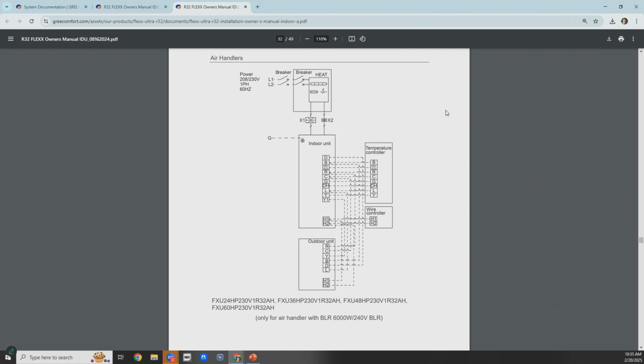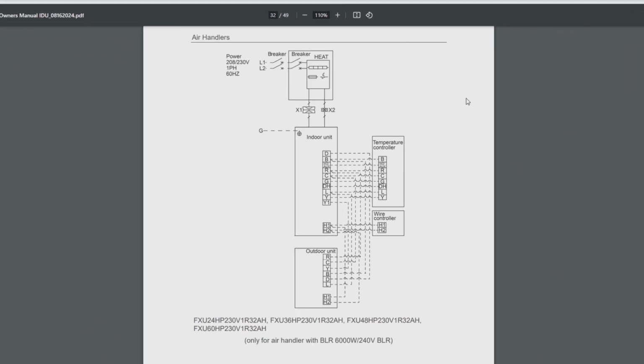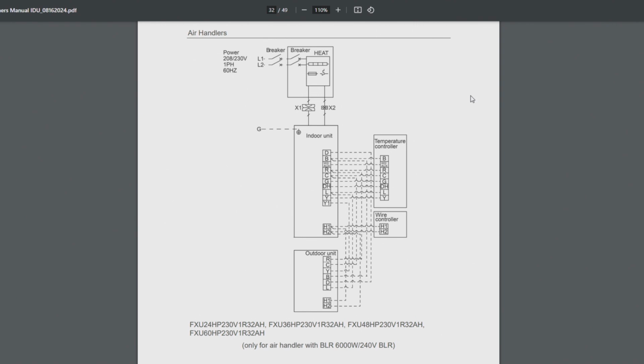Once it goes into alarm, if the detection sensor is able, it turns the blower on high speed, turns the outdoor unit off, or turns auxiliary heat off, which we're going to show you in the video, that it does work that way. And then you get an audible alarm, and an error code, if you're using GREE's controller, is produced on the, well, I think it's, JD, didn't it say something like refrigerant leak detection? Yep, the RS-485. Yes. So anyway, it says you've got a refrigerant leak.